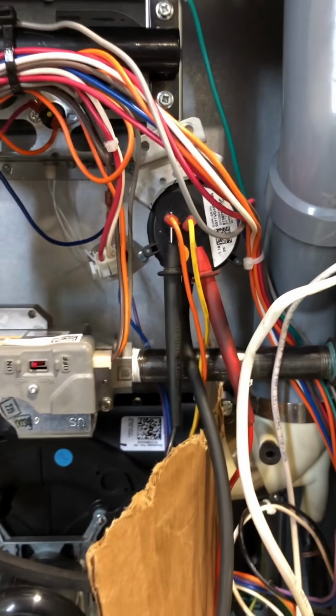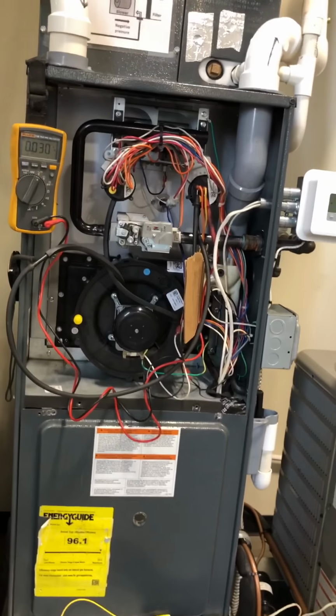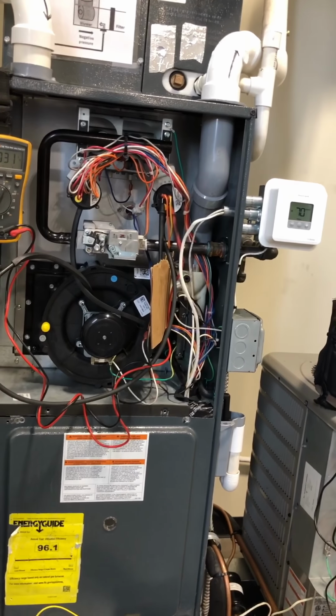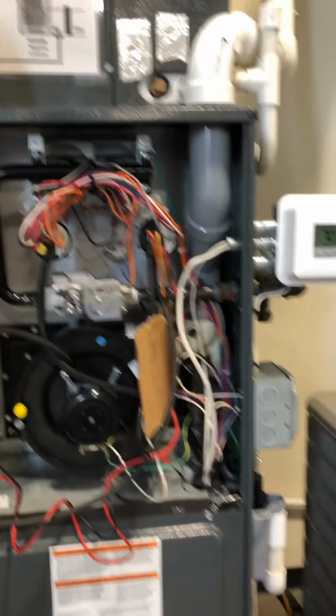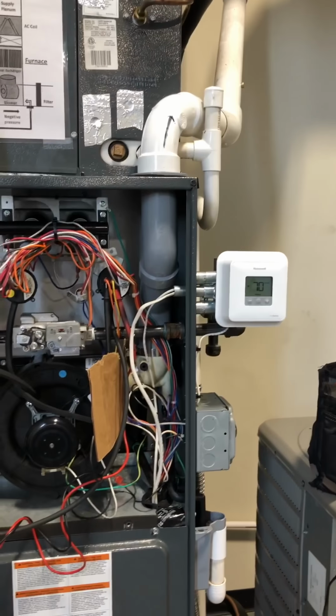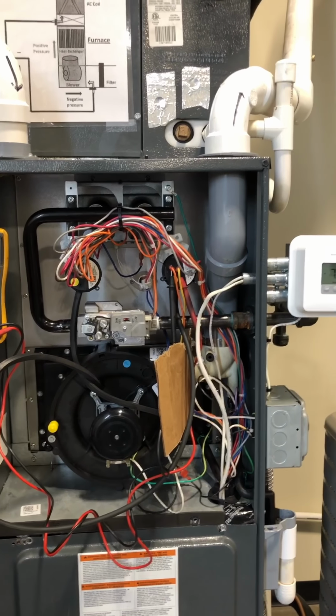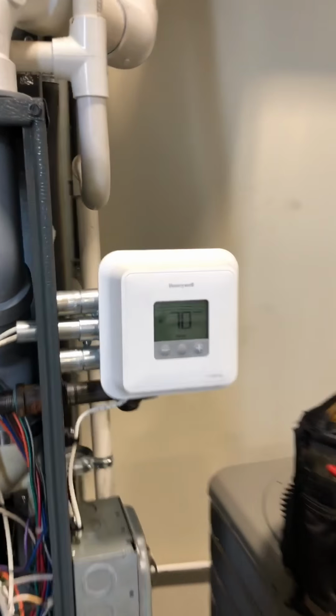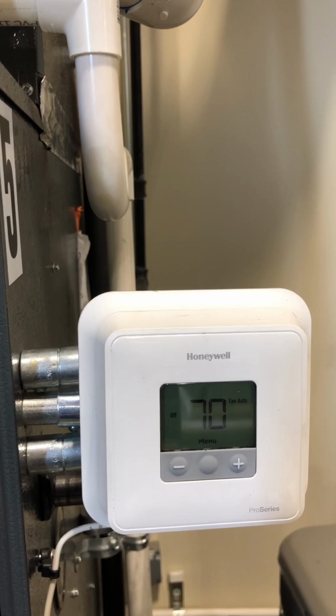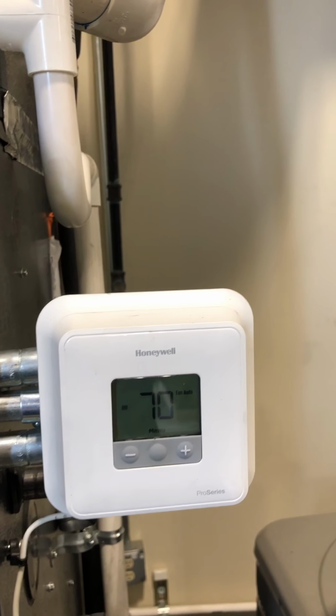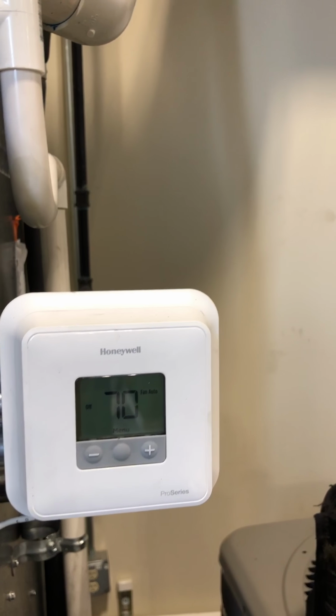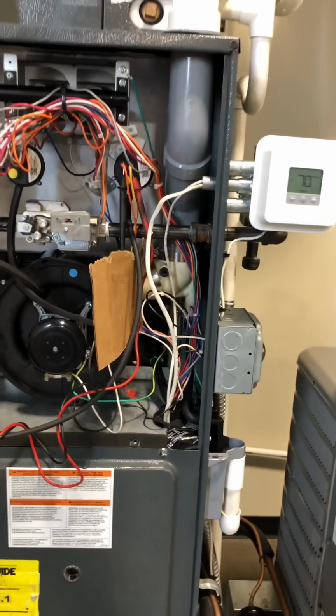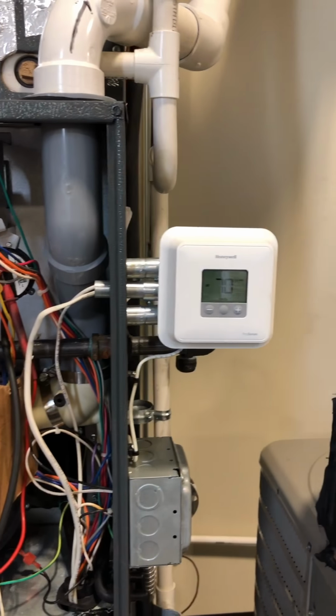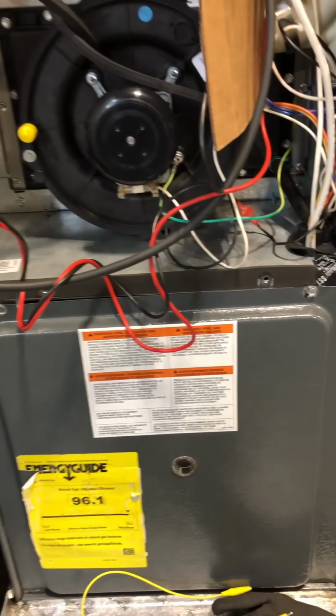We're going to see what that's pulling here. So remember the sequence of operation on these things, and there's always going to be a little bit of debate about what I'm about to say, but from the tests that I've done, it's the way that I go by. Call for heat from the thermostat. Number one, always number one. We can't do anything unless that thermostat's saying so. So if that thermostat isn't saying anything, or it's off, and your furnace is trying to start up, well, you got a problem.